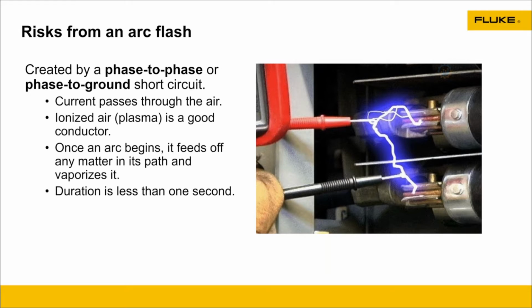The current could literally pass through the air. Ionized air is a great conductor of this. And as you can see in this picture here, these test leads are there. There's a lot of exposed metal. They're touching high voltages, high current, and then arc flash begins.